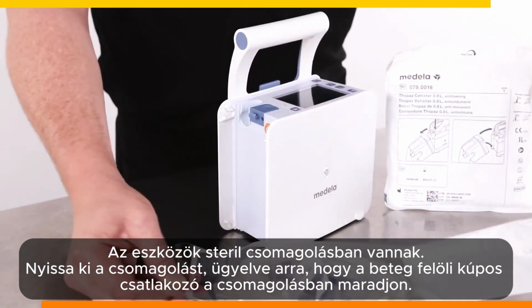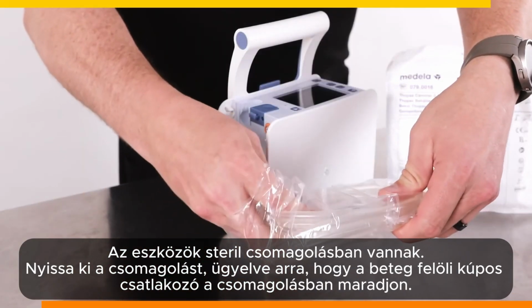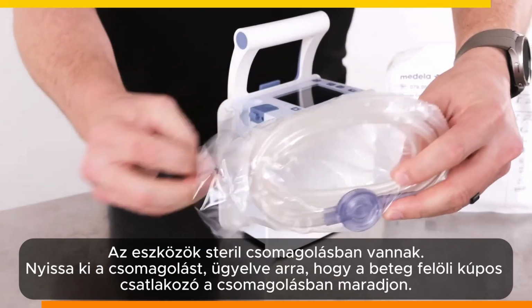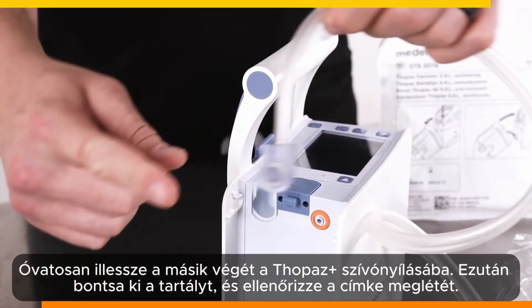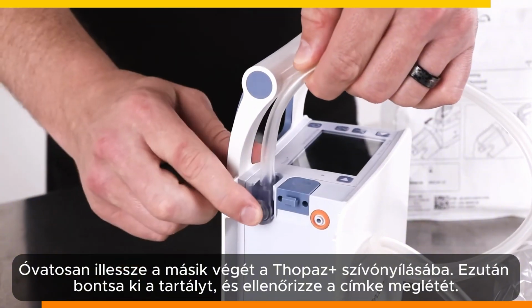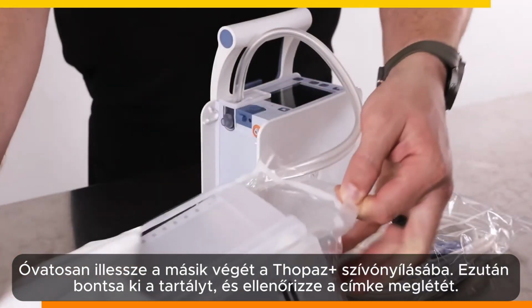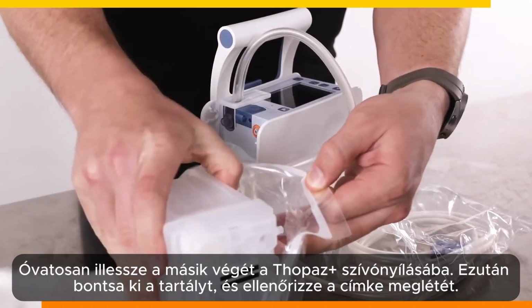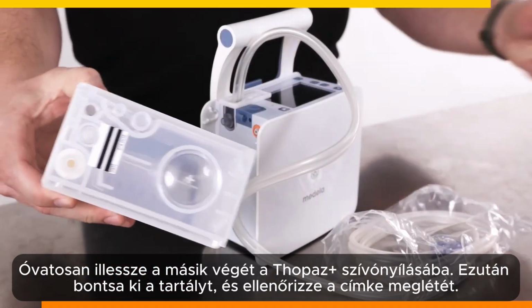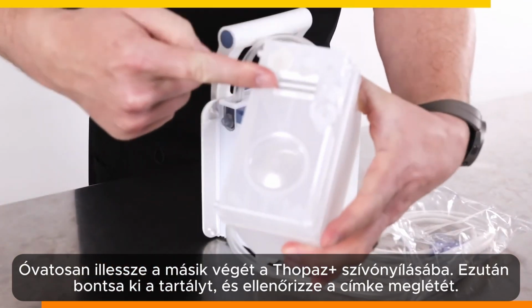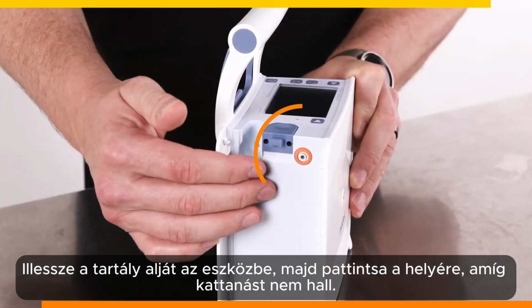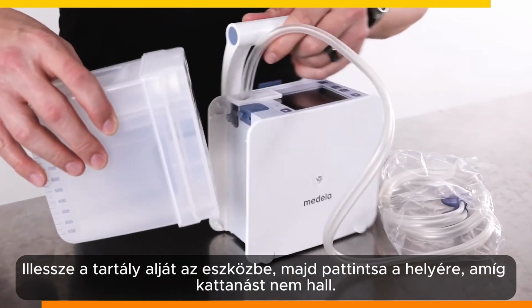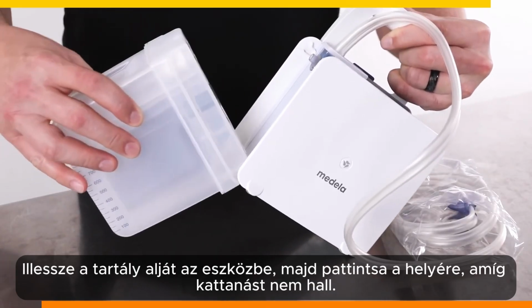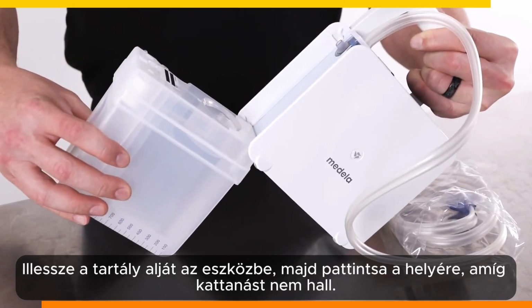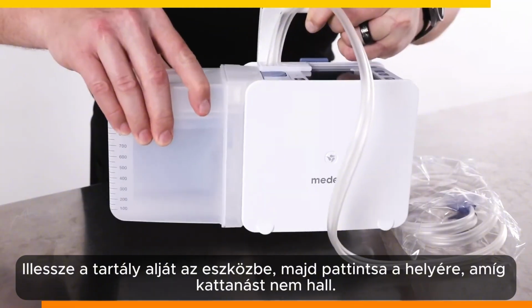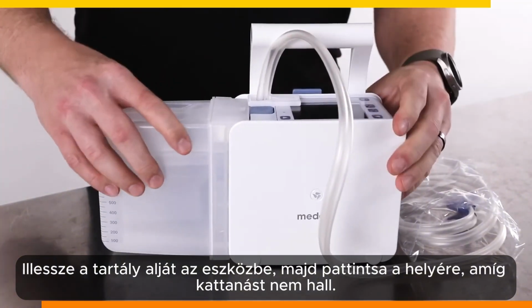Carefully open one end of the tubing packaging, ensuring that the pointed patient connector end remains sterile. Carefully insert the other end into the Thopaz+ suction port. Next, open the canister and check to ensure that the canister detection label is present. If it is not present, do not use the canister. Ensure that the orange O-ring is present, and take the canister and fit the feet first at the bottom of the device. Then rock and lock the canister into place until you hear a click.